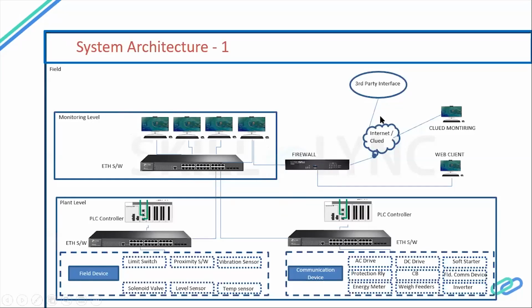If required by a third-party interface, we need to connect your storage server, or web client, or OPC server directly through a firewall. Why am I creating one PC only for the firewall? Why am I not connecting directly here? Due to cyber security. In this PC, two network cards are installed, one for the internal network only, and one for outer internet purposes. Whatever data is required for my third-party interface, we use only that. If somebody hacks, the damage comes only up to here, and does not go beyond this point. So this is for cyber security purposes.